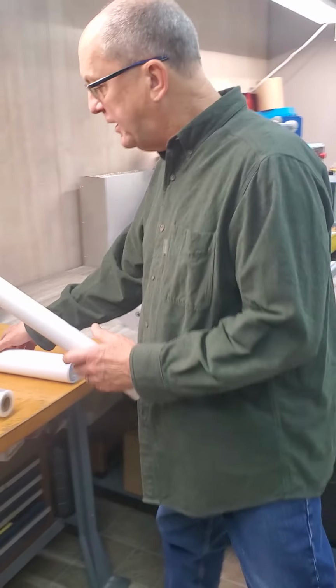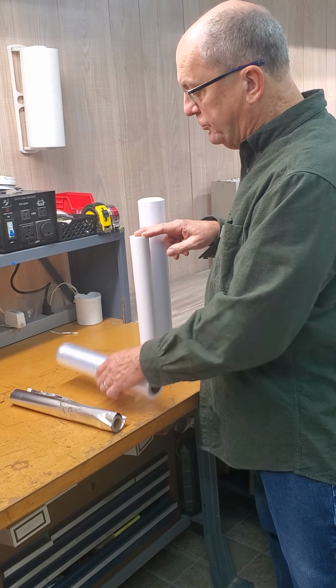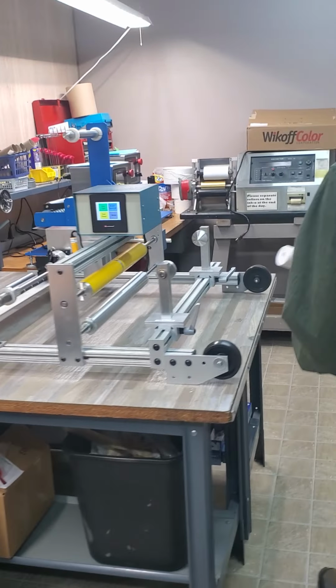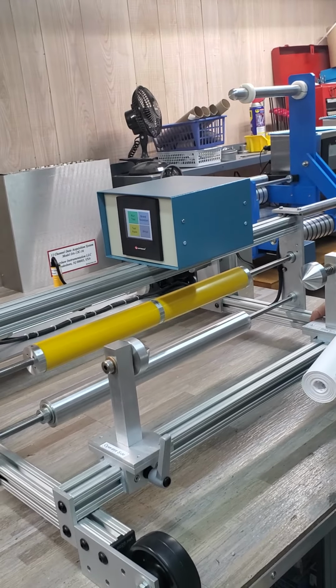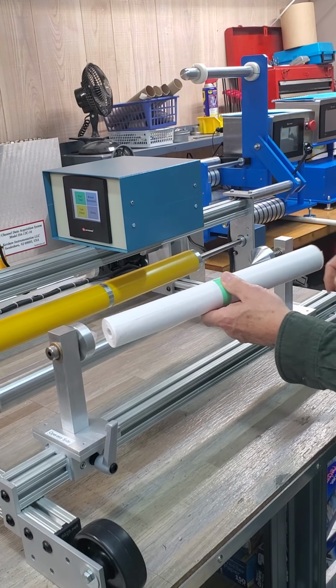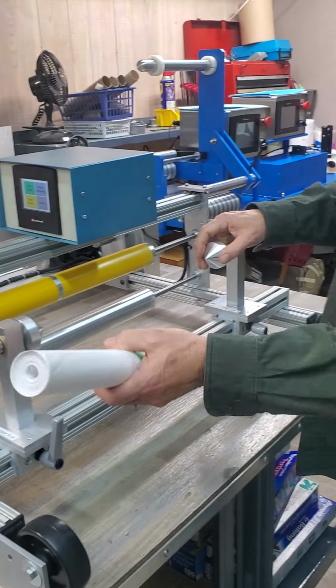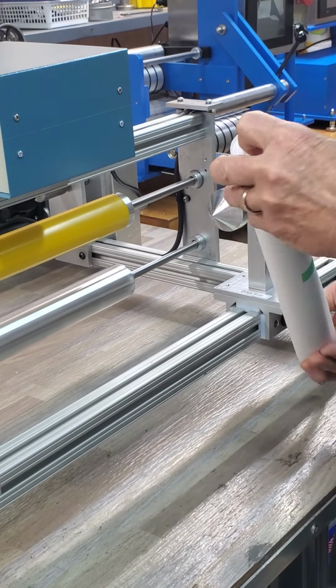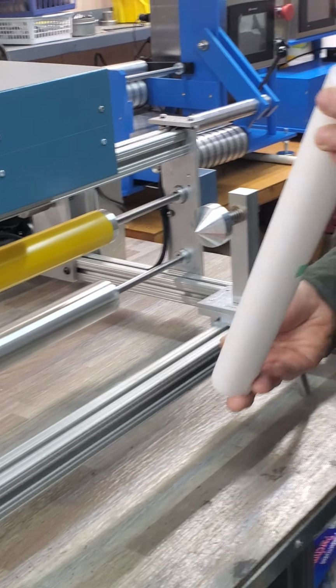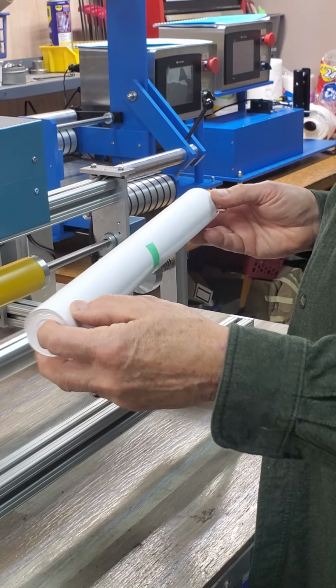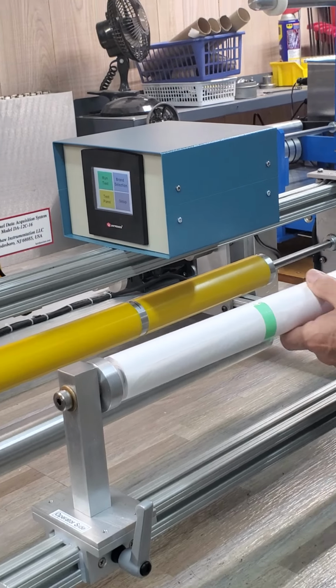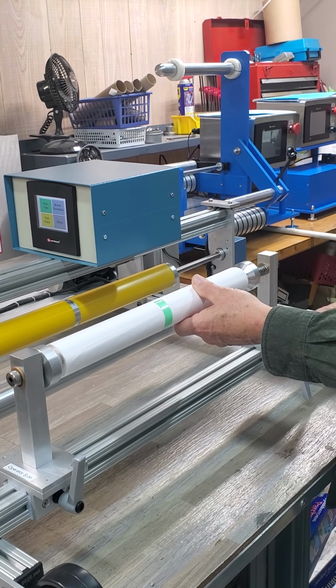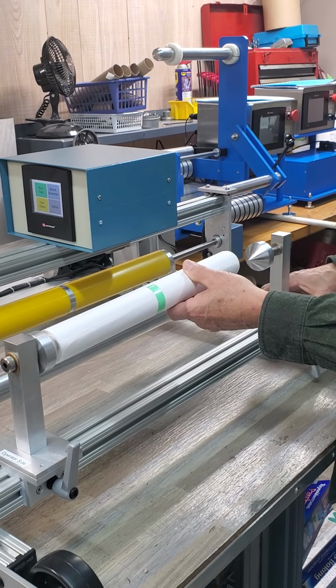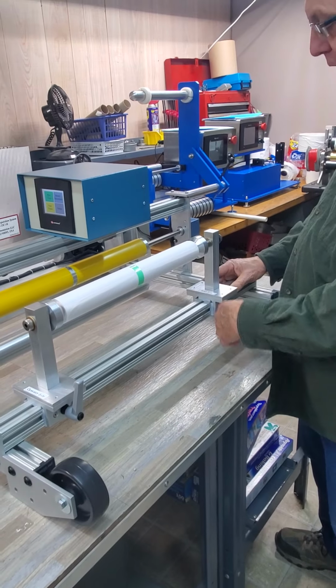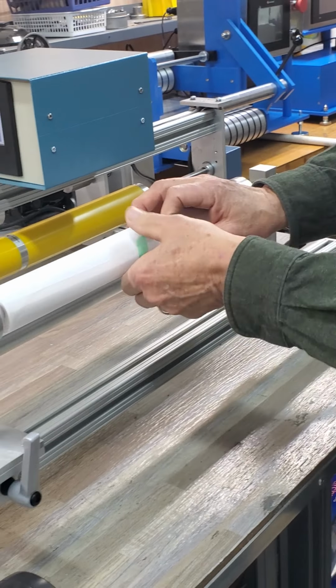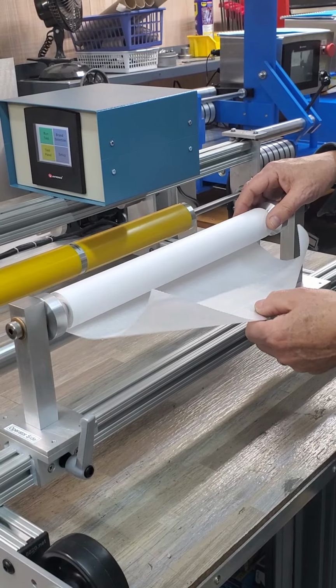For starters, you'll notice that these samples that I have are all different lengths. So what we have designed is the stations are adjustable to accommodate the length of the product. For example, on the unwind station, we have these cones that support the roll. And the reason we have the cones is because some of these products don't have a core, so we don't have clearance to have a shaft. So we have cones that support the roll, and you can see this right-hand cone, which I refer to as the drive side, is adjustable, and it is also spring-loaded, so we can apply a little spring force to that, which will put a little drag on our test sample.